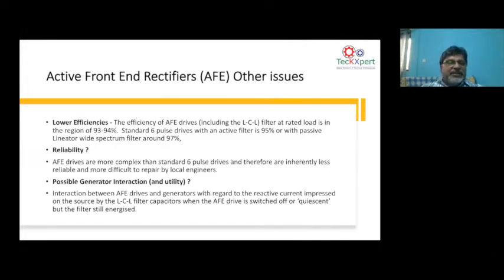Active front-end drives have lower efficiency. When it comes to the active harmonic filter versus the active front-end drive, the efficiency of the active front-end drive is about 93%. For an active filter, it's about 95%. But if you go for a passive broadband filter, it's 97%. So whether you go for an active front-end drive, an active filter, or a high-pass filter for a VFD has to be decided based on these engineering aspects. A high-pass filter gives you much higher efficiency. It has its own benefits. An active front-end drive has its benefits and its own demerits. An active filter has its plus and minus. So ultimately, right engineering means you have to select the right choice.